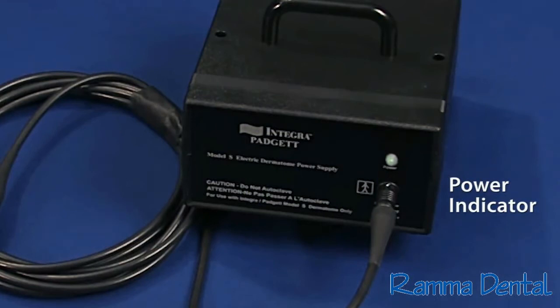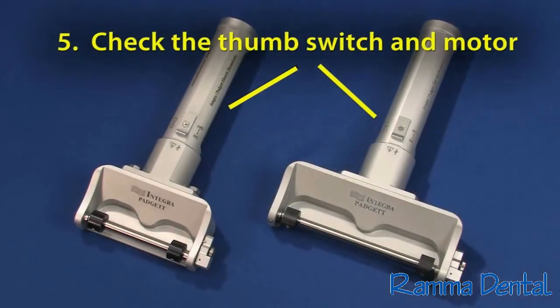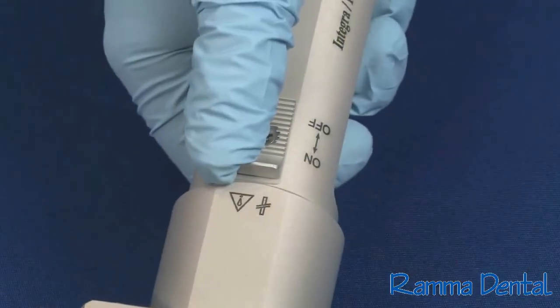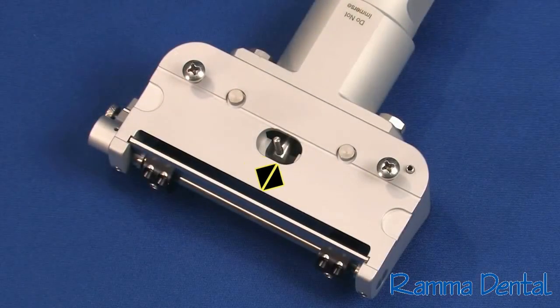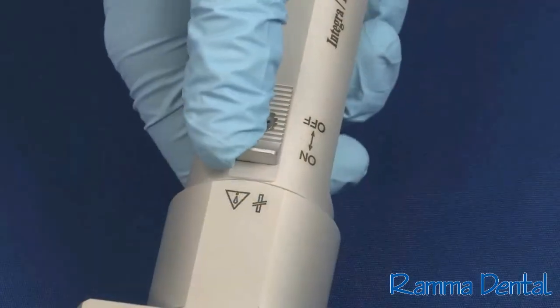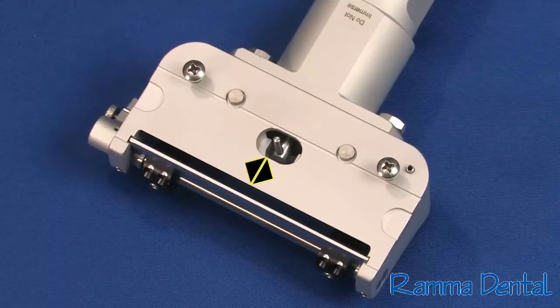If the indicator light does not illuminate, see the power supply section of the user manual. Also, confirm that voltage is available at the wall receptacle. 5. Depress the thumb switch on the Dermatome handpiece momentarily. The Dermatome motor is to run, and the oscillating pin is to move rapidly from side to side. Note any unusual motor sounds.